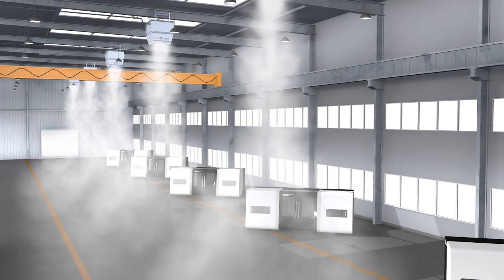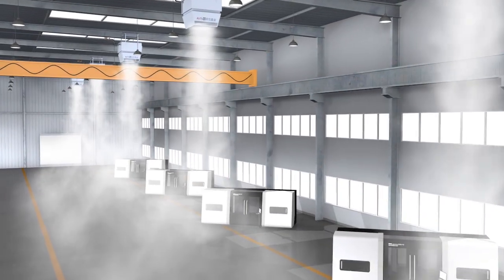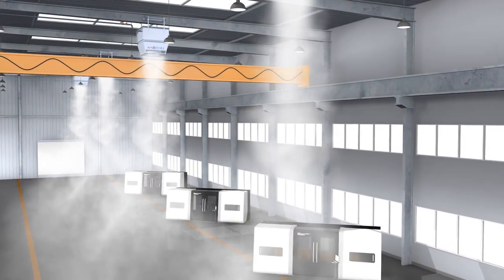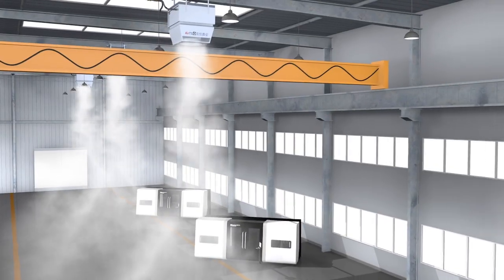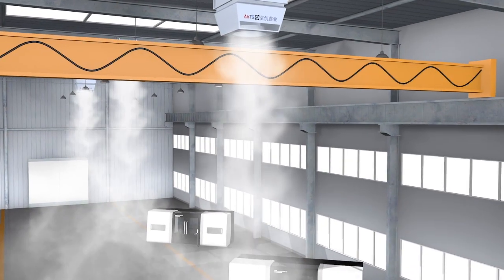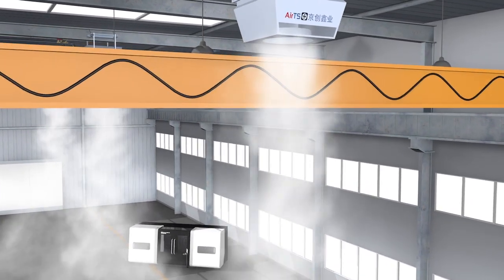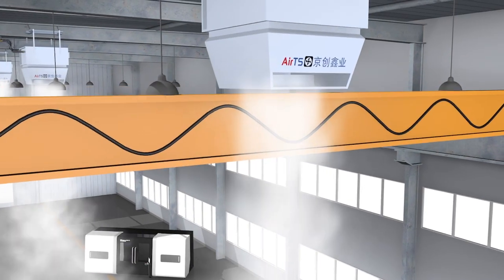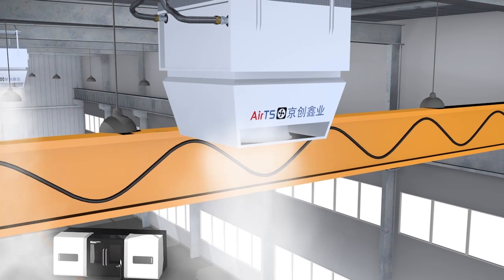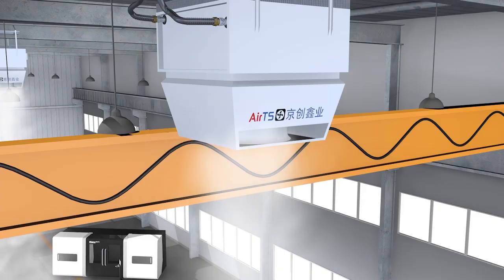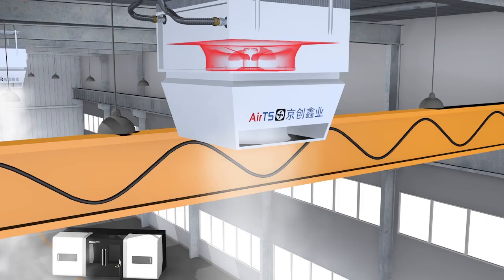The cleaning and maintenance of filter screen of the HVAC unit is critical to the proper use of the equipment. During the long-term use, the equipment filter screen will be covered with dust, resulting in unsmooth return air, which will directly affect the cooling, heating, fresh air, exhaust and heat recovery performance of equipment. If the filter screen is blocked seriously, it will also cause the fan overheat and even damage.